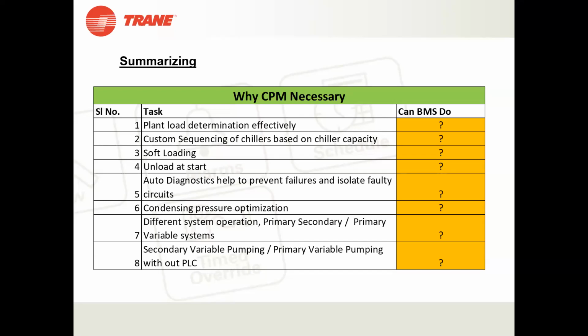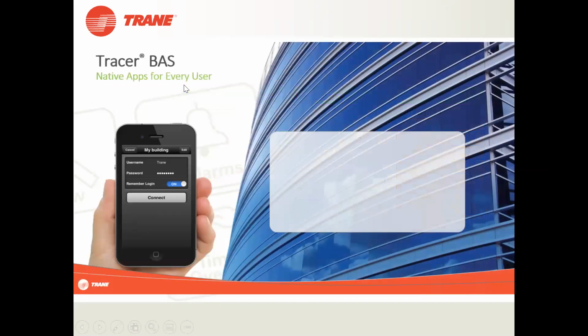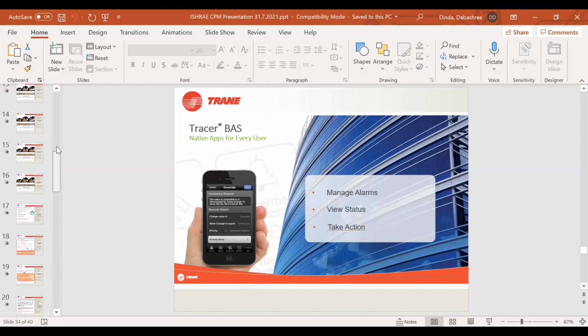As Debashri mentioned in her slides, we classify the HVAC system into the low side and high side. Whatever is there above the pumps is high side; below pumps is low side. So the chiller plant manager mainly concentrates on the high side equipment, which are chillers, pumps, and cooling towers, whereas on the low side you have your AHUs with VFDs and VAV systems.